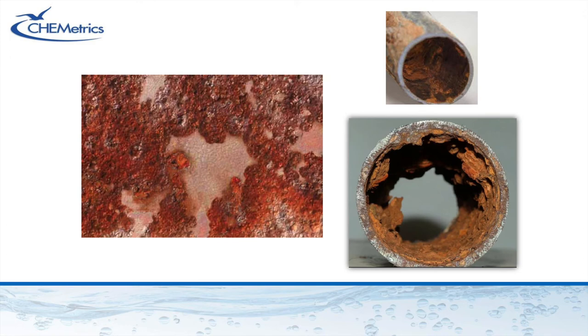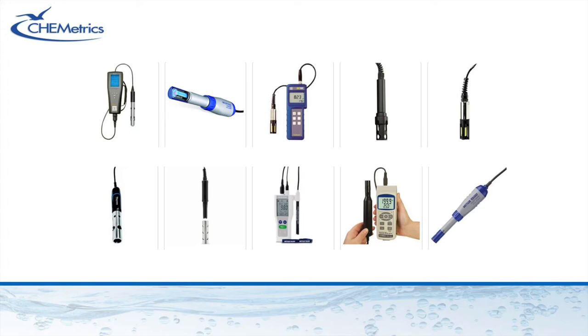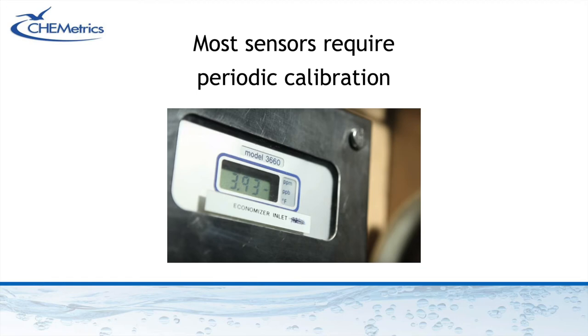The problem is that competing chemical reactions between oxygen and boiler surfaces are likely to occur, resulting in system corrosion. That means routine monitoring is crucial to confirm you've been removing enough DO. You can turn to optical and electrochemical inline probes, but while these online analyzers offer continuous DO measurement, they require routine calibration and those calibrations can drift. The analyst must also ask whether sensors are beginning to corrode or whether online results are being compromised.